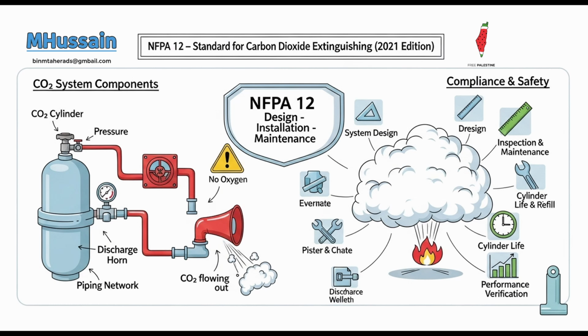Essentially, yes. It's crucial to understand that these are not a substitute for fixed extinguishing systems in most cases. Not a replacement for automatic systems. Right. They are primarily used in very specific scenarios where the hazard is either inaccessible to fixed protection, perhaps a constantly moving target, or an irregularly shaped area, or consists of scattered individual hazards that cannot be economically or adequately protected by fixed nozzles. For tricky or spread out hazards. The authority having jurisdiction, or AHJ, ultimately makes that determination, often balancing practicality with the utmost safety.